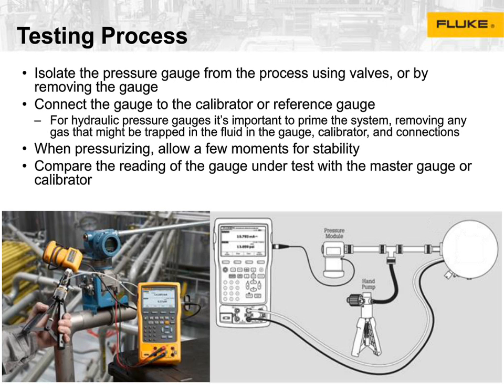And then we talked about letting the system sit, especially for higher pressures, and then you basically do a comparison. So the procedure is pretty simple. One thing I'd like to point out here, in this picture on the lower left, and the difference between the diagram on the right and the picture on the left, is in the lower left you see that the pressure module, or the reference gauge, is directly attached to the pump, unlike the way it's set up here in the diagram. This setup on the left is far superior.